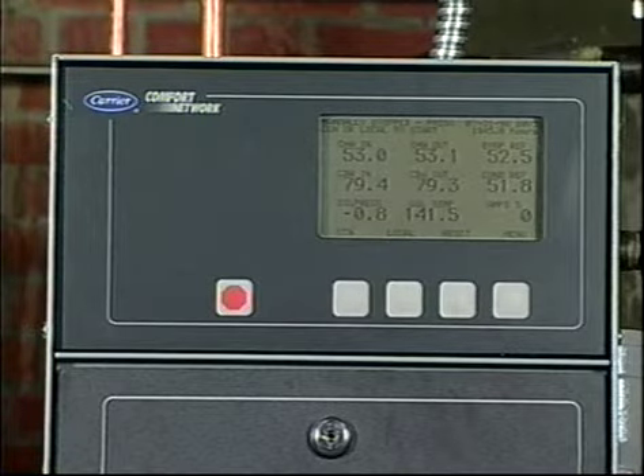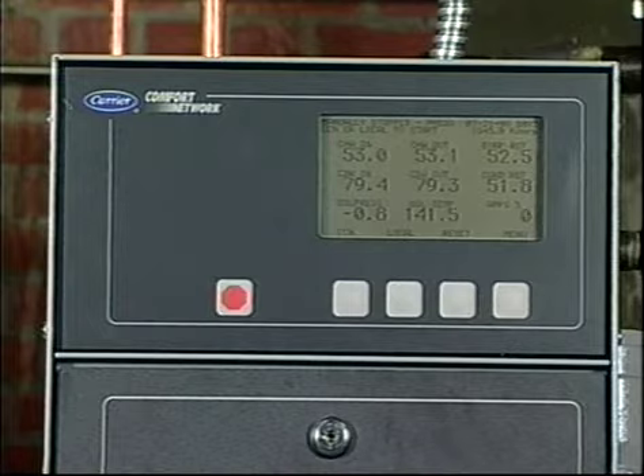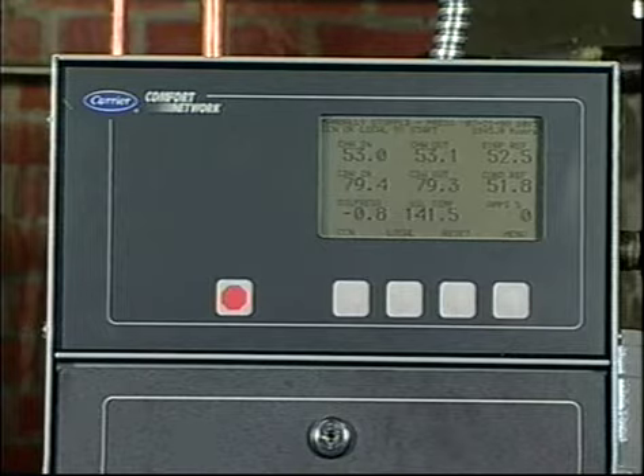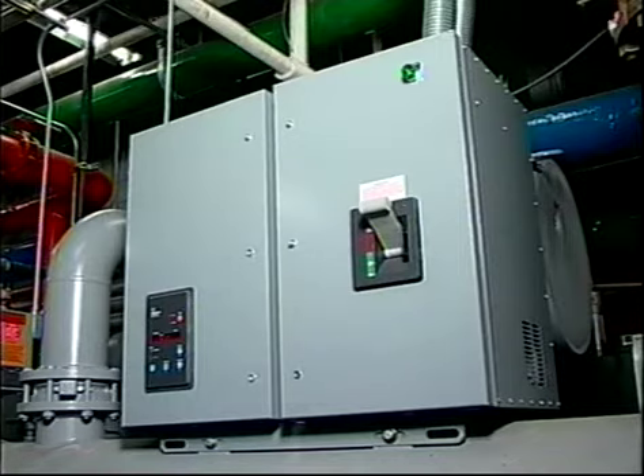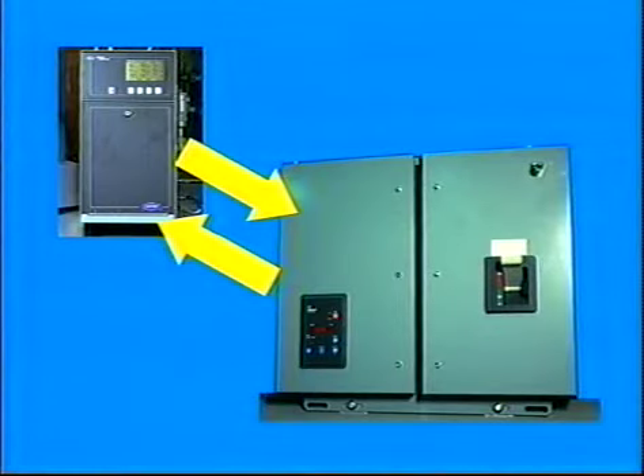Mounted in the control center is a device called a LID, Local Interface Device, which allows the operator to start and stop the chiller, read data, and enter operating parameters. The starters for the compressor and other motors are located in the starter cabinet next to the compressor or in a freestanding cabinet. The Control Center module communicates with the Starter Management module. Amperage, voltage, and operating information is relayed between the two modules. This operating information can be displayed on the LID by pushing the status function soft key.